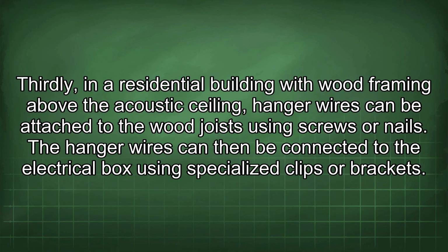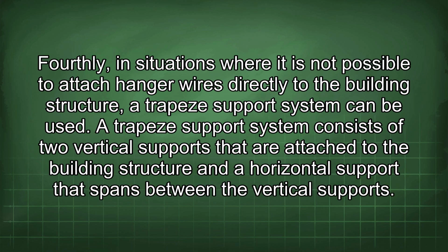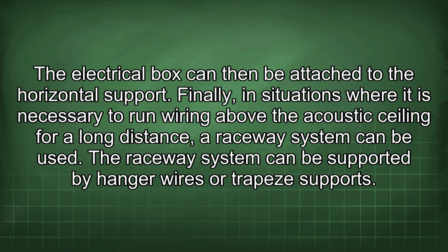Thirdly, in a residential building with wood framing above the acoustic ceiling, hanger wires can be attached to the wood joists using screws or nails. The hanger wires can then be connected to the electrical box using specialized clips or brackets. Fourthly, in situations where it is not possible to attach hanger wires directly to the building structure, a trapeze support system can be used. A trapeze support system consists of two vertical supports that are attached to the building structure and a horizontal support that spans between the vertical supports. The electrical box can then be attached to the horizontal support.